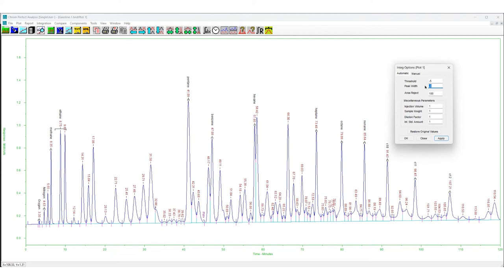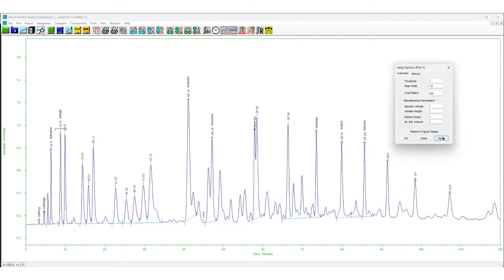Peaks that are much wider than the peak width parameter may or may not be detected. Wide peaks that only slightly exceed the threshold are usually not detected, but large, wide peaks that greatly exceed the threshold are often detected regardless of the peak width setting. Therefore, when the signal-to-noise ratio is large, the peak width setting is not critical.